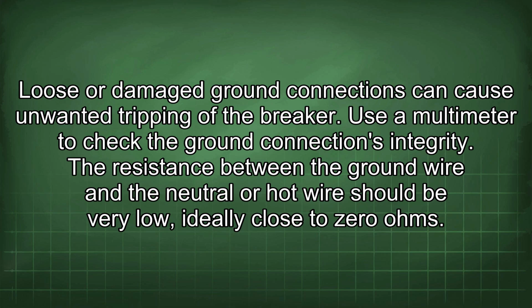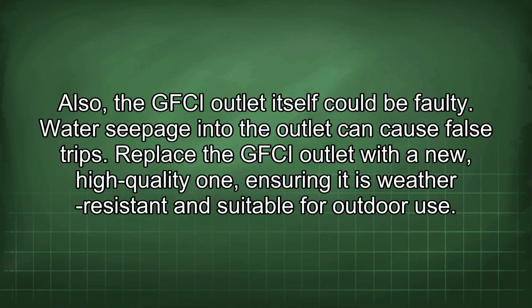Use a multimeter to check the ground connection's integrity. The resistance between the ground wire and the neutral or hot wire should be very low, ideally close to 0 ohms. Also, the GFCI outlet itself could be faulty. Water seepage into the outlet can cause false trips. Replace the GFCI outlet with a new, high-quality one, ensuring it is weather-resistant and suitable for outdoor use.